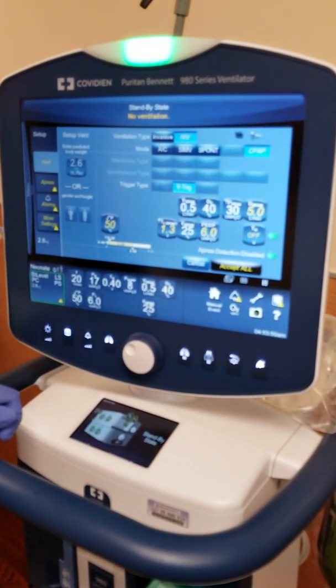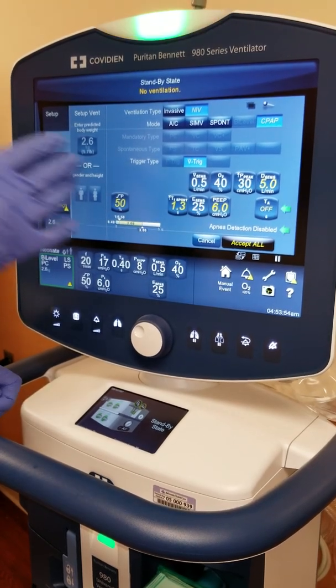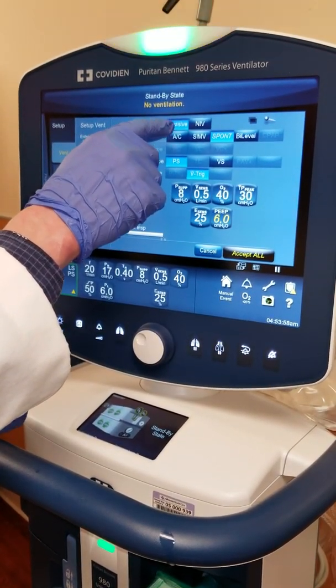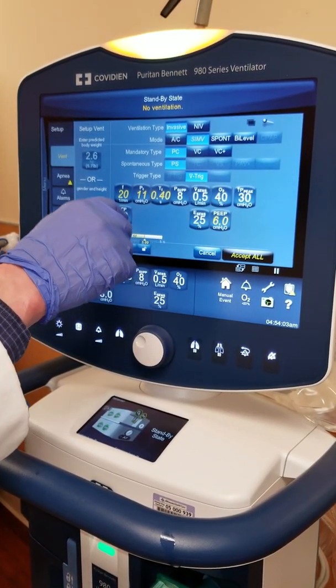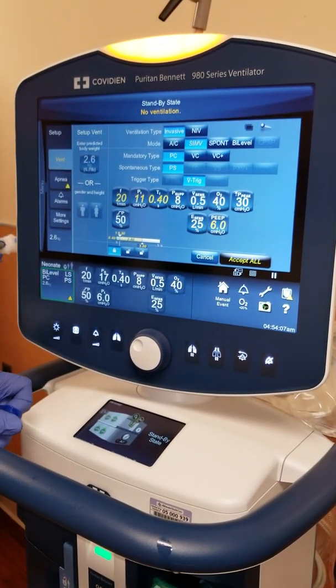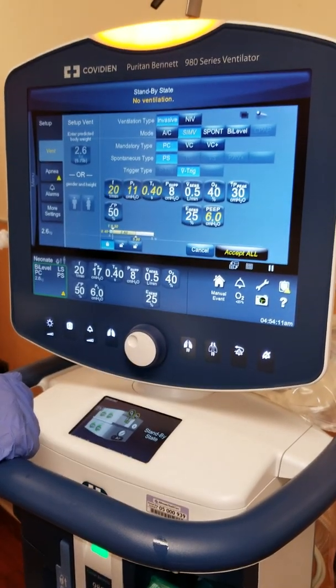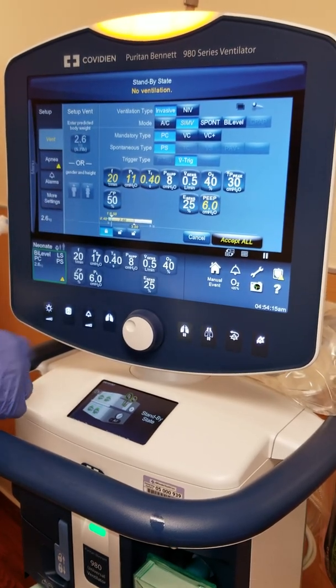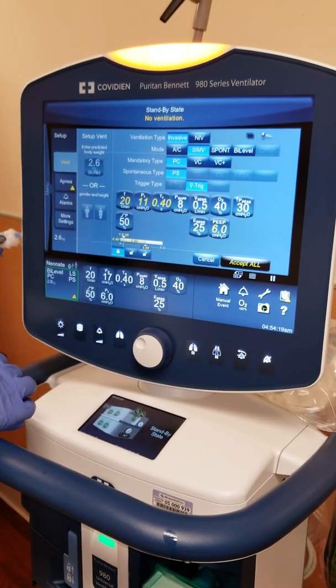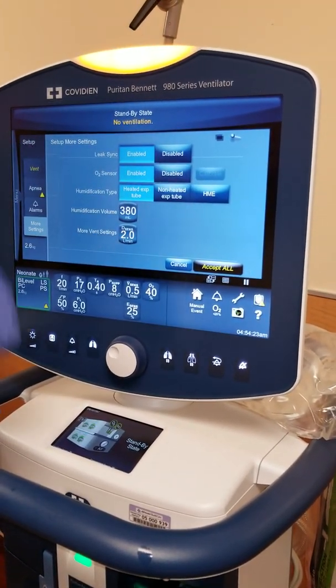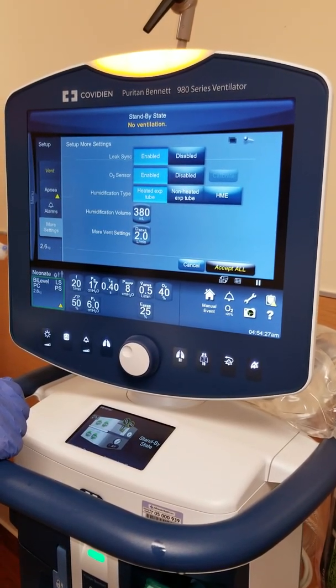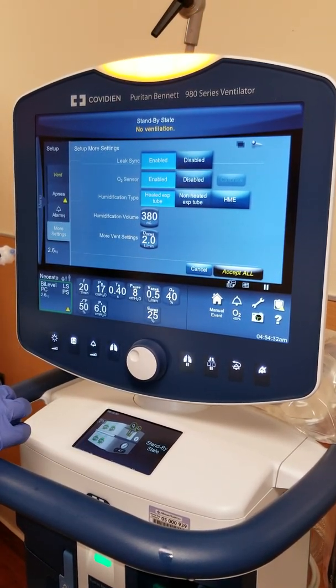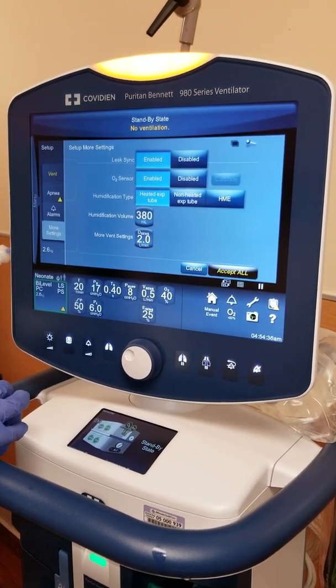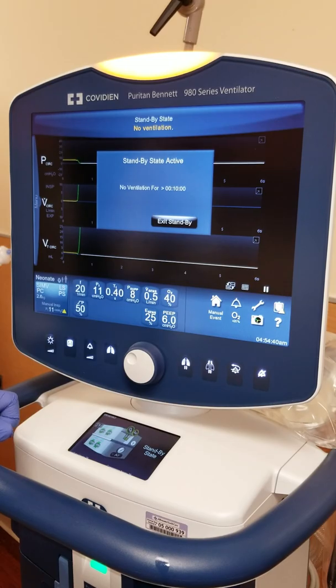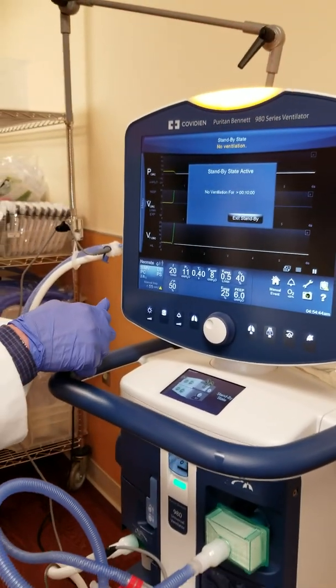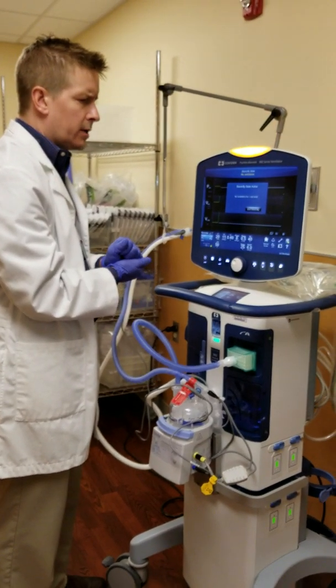If you need a little bit more extra support, like a rate and an inspiratory pressure on top of the CPAP, you might want to try a little something like this. You can go into an invasive pressure SIMV, and then with a backup rate 20 to 30, an inspiratory pressure of 21 to 23. You can let the neonatologist drive that. I time is 0.4, pressure support 8. And what this will have in the background is leak sync. So whenever this RAM cannula leaks, it will compensate for it. And it's enabled on a default. So that's pretty slick. And what we will investigate further is possibility of using a BiPAP modality on some of these neonatal interventions.